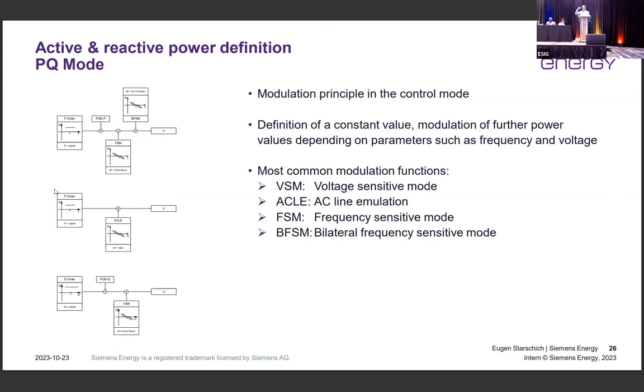For example, if you have 1000 megawatt, I say I want 500 megawatt constant, and for the remaining 500 megawatts I want the power to depend on the phase angle. So this is a kind of combination with an AC line. The HVDC system is operating as an AC line, but with a certain offset of the active power. This gives you maximum flexibility, and this is what has already been mentioned by Johannes. To utilize all this functionality, you also need to design tools in your network to use the functionality of the systems. If you use it constantly as constant power, that's fair enough, but you are not utilizing the full capabilities of the HVDC system.